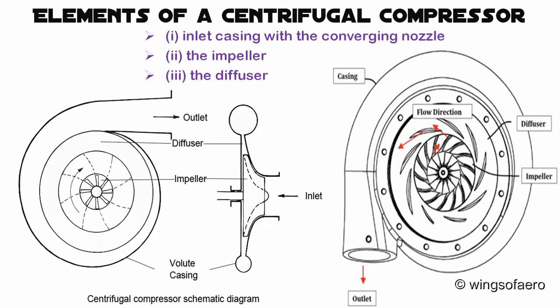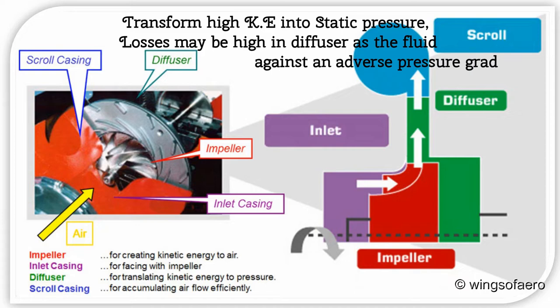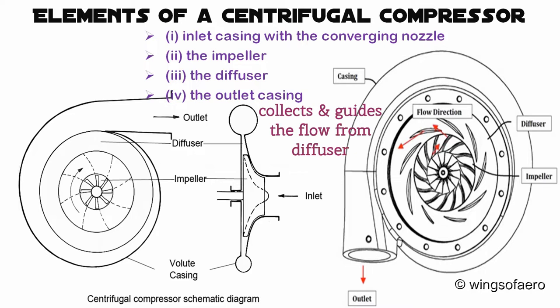The diffuser's function is to transform the high kinetic energy of the fluid at the impeller outlet into static pressure. The main aim of providing diffusers is to increase static pressure by reducing kinetic energy. The outlet casing comprises a fluid collector, also known as the volute.